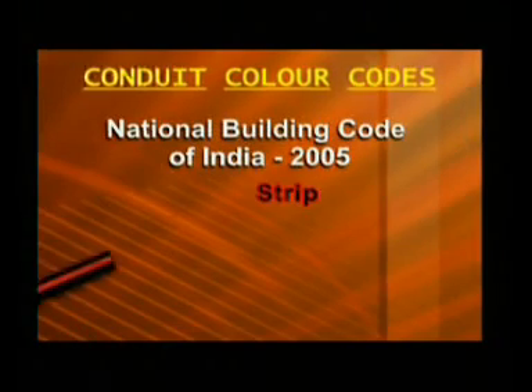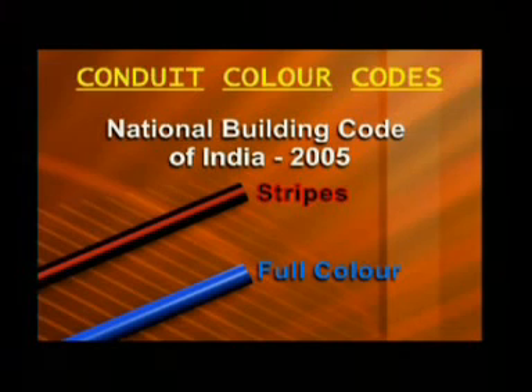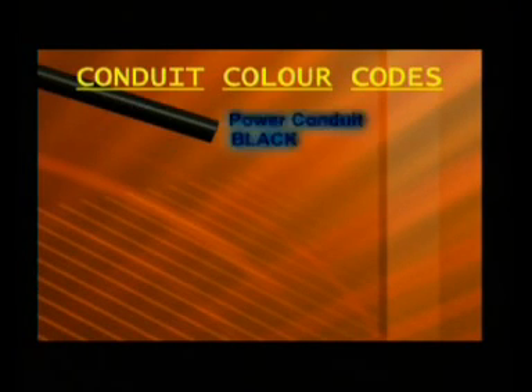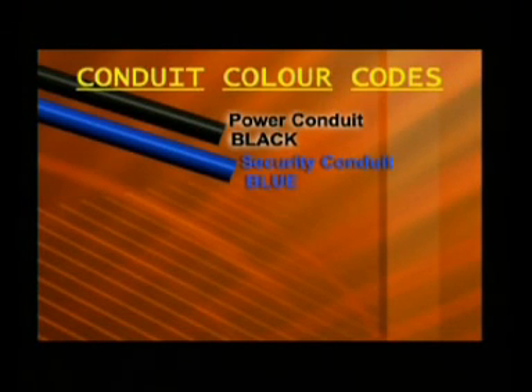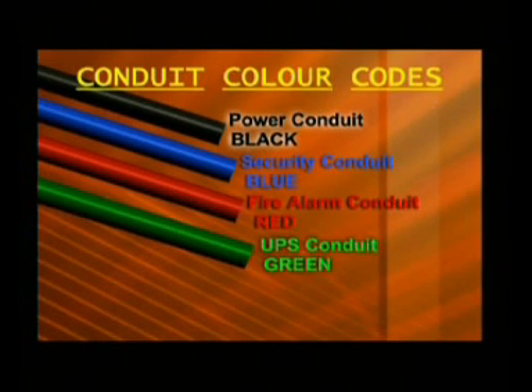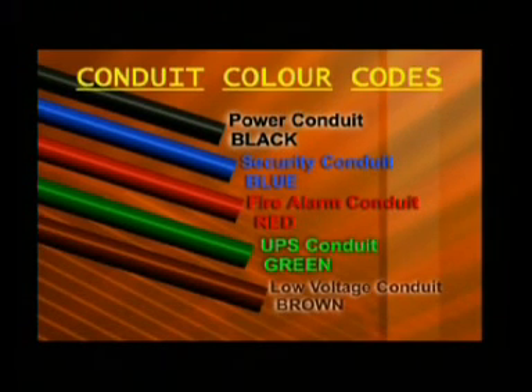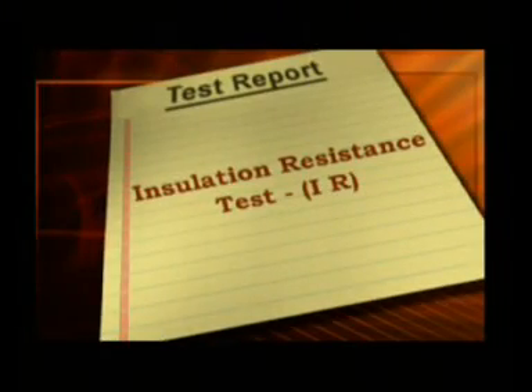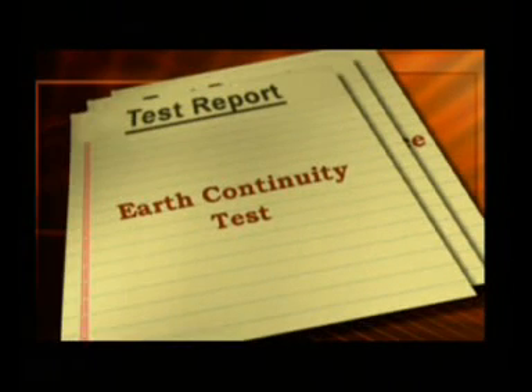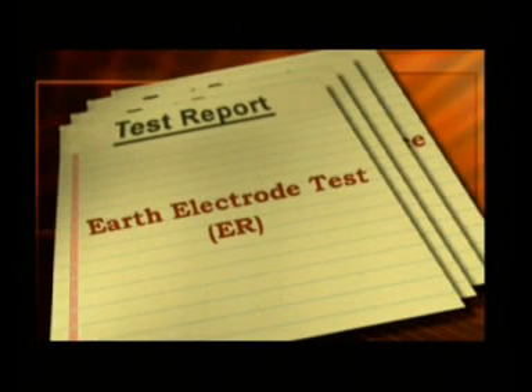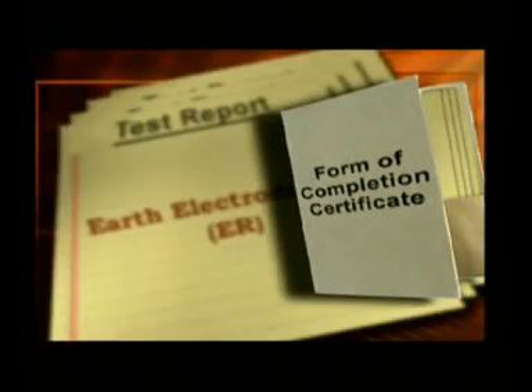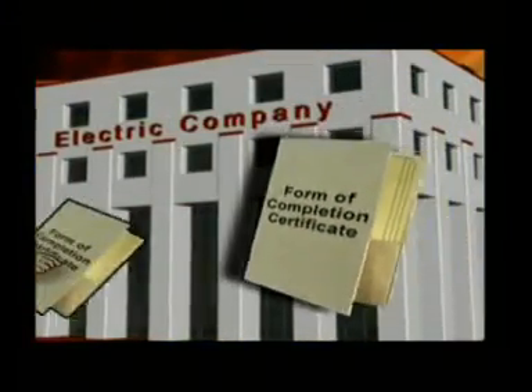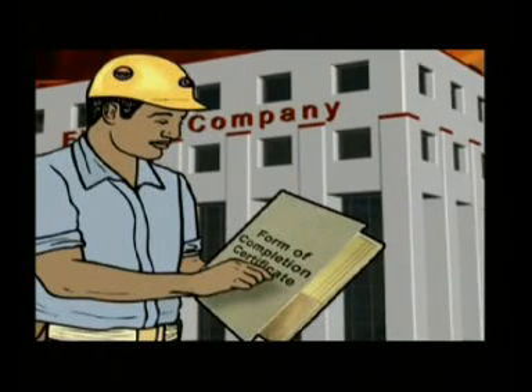The color code will be depicted either by a stripe or by the color of the conduit itself. The color scheme for the wires is as follows: power conduit black, security conduit blue, fire alarm conduit red, UPS conduit green, low voltage conduit brown. Certain things are needed to be done after the installation is over. Insulation resistance test, polarity test, earth continuity test and earth electrode test are conducted after the electrical work is over. The results of all these tests are recorded in a test report called the Form of Completion Certificate and submitted to an officer or engineer of the electricity company before proceeding any further.